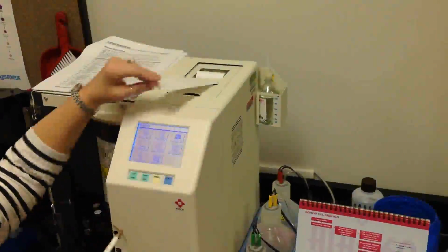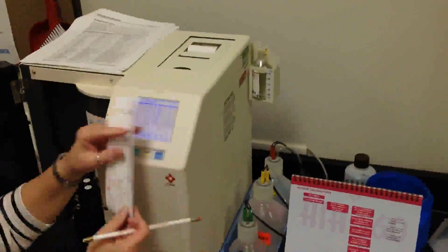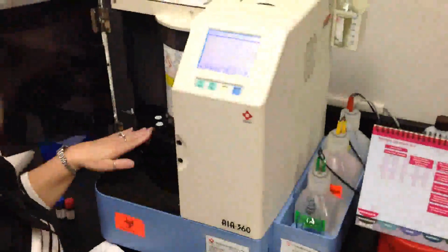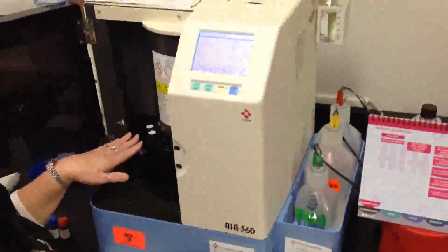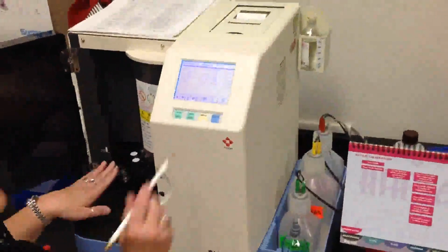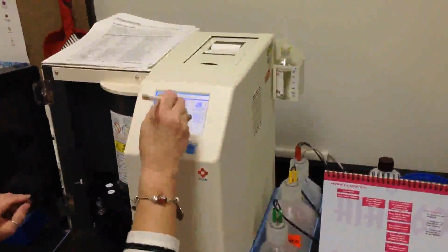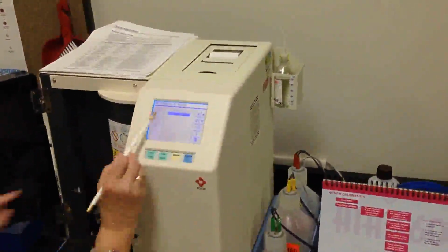assay monitor, I need to run controls to verify that this calibration is where we want it to be. I've previously pipetted 2 levels of controls with 1 sample size and 1 dead volume for a total of 200 microliters. Now I need to go to the main menu.